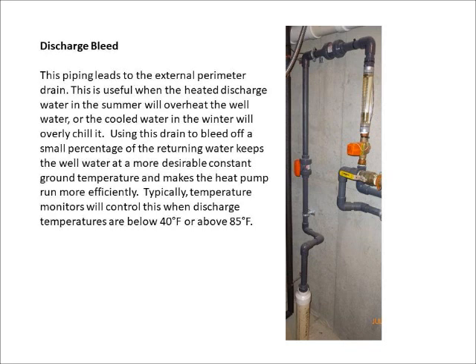This is useful when the heated discharge water in the summer will overheat the well water, or the cooled water in the winter will overly chill it. Using this drain to bleed off a small percentage of the returning water keeps the well water at a more desirable constant ground temperature. It makes the heat pump run more efficiently. Typically, temperature monitors will control this when discharge temperatures are below 40 or above 85 degrees Fahrenheit.